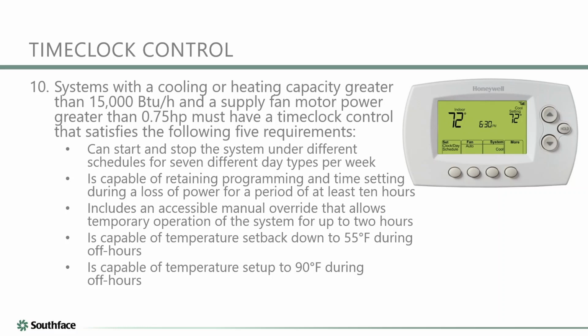And then you also need an accessible manual override that allows for temporary operation of the system for up to 2 hours. Again, just temporary. You don't want them just to lock it out and put it in manual mode, and again, just leave it that way. And then you need a setback down to 55. This is a wintertime condition, and then 90 in summertime condition. These setback periods are based on occupancy. You don't really need to run the heat or the cooling while the building is unoccupied. So any other things to add here when we're talking about timeclock controls and thermostats?